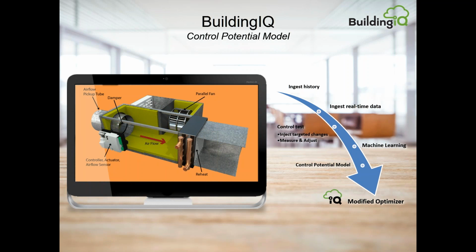The other model is what we call a control potential model. Again, this is a deep data-based understanding of how the BMS responds. So if you want to push temperature half a degree in one zone up and half a degree in another zone up and they're adjacent, what does that really mean in this system? It's captured in data so you can always predict what that system is doing. At the end of the day, you get a deep database understanding of the system to go along with your expert level understanding of how that building reacts as a facility team. So you've got the human expertise combined with the data expertise, and that is a control potential model. So you'll always know how the system will react under any given circumstance, particularly weather, occupancy, equipment changes. It's all beginning to be modeled for you, right? And so that's another key model.